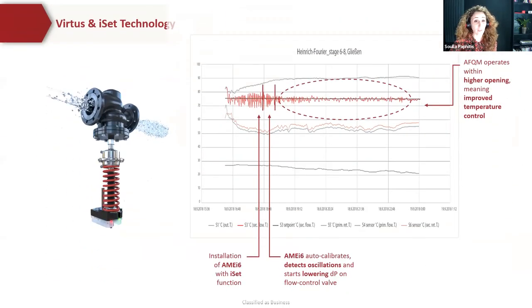So with the use of our latest technology, which is the Virtus PICV and autonomously controlled intelligent actuator, which is the ISET, you have the ability to change the differential pressure over the motorized control valve. And this ensures flow stability for high and low flows, with the added benefit of a more compact design and added setting indicator. The split characteristics of the Virtus PICV offers improved control and higher accuracy. The intelligent differential pressure adjustment ISET actuator improves network efficiency by offering continuous auto commissioning and providing pump cost optimization, and can offer predictive maintenance when it's being monitored.